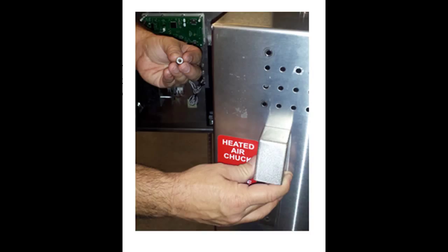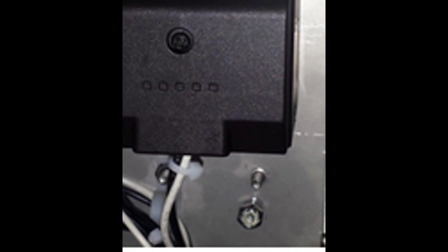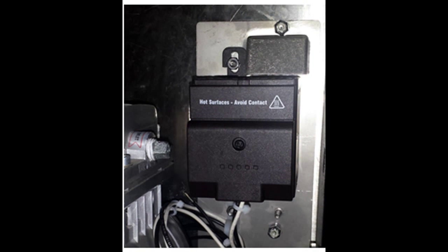Temporarily install the chuck holder by hand tightening one of the 10-32 lock nuts provided on the chuck holder's top mounting stud. Use the slot on the top of the heater mounting bracket to locate and align the heater assembly. The chuck holder's lower mounting stud should pass through the heater mounting bracket. Install the second nut on the lower stud as shown, then tighten both lock nuts.